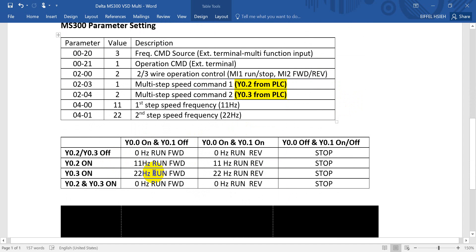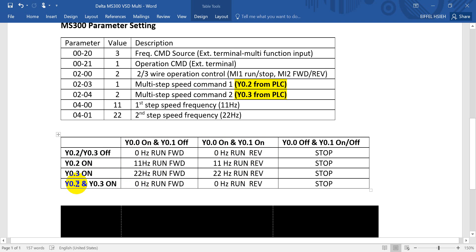When Y0.0 is off, that means stop. When Y0.2 and Y0.3 are on and Y0.1 is on together with Y0.0, the motor will go in reverse. One important point: if both multi-speed digital inputs are on simultaneously, the frequency command will become zero.